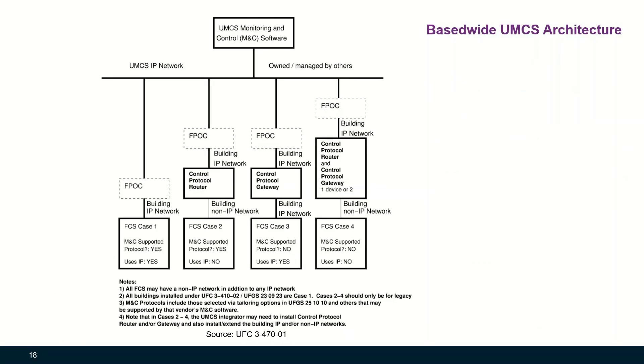Let's look at the base-wide utility monitoring and control system (UMCS) architecture. The UMCS monitoring and control software usually resides on a BAS operator workstation. UMCS also monitors other systems beyond just building automation systems, and is typically owned or managed by others, not facility management. The facility control system (FCS) is basically the building automation system discussed earlier, without the server and operator workstation (or UMCS front-end). The building control network is called the building IP network in this architecture.